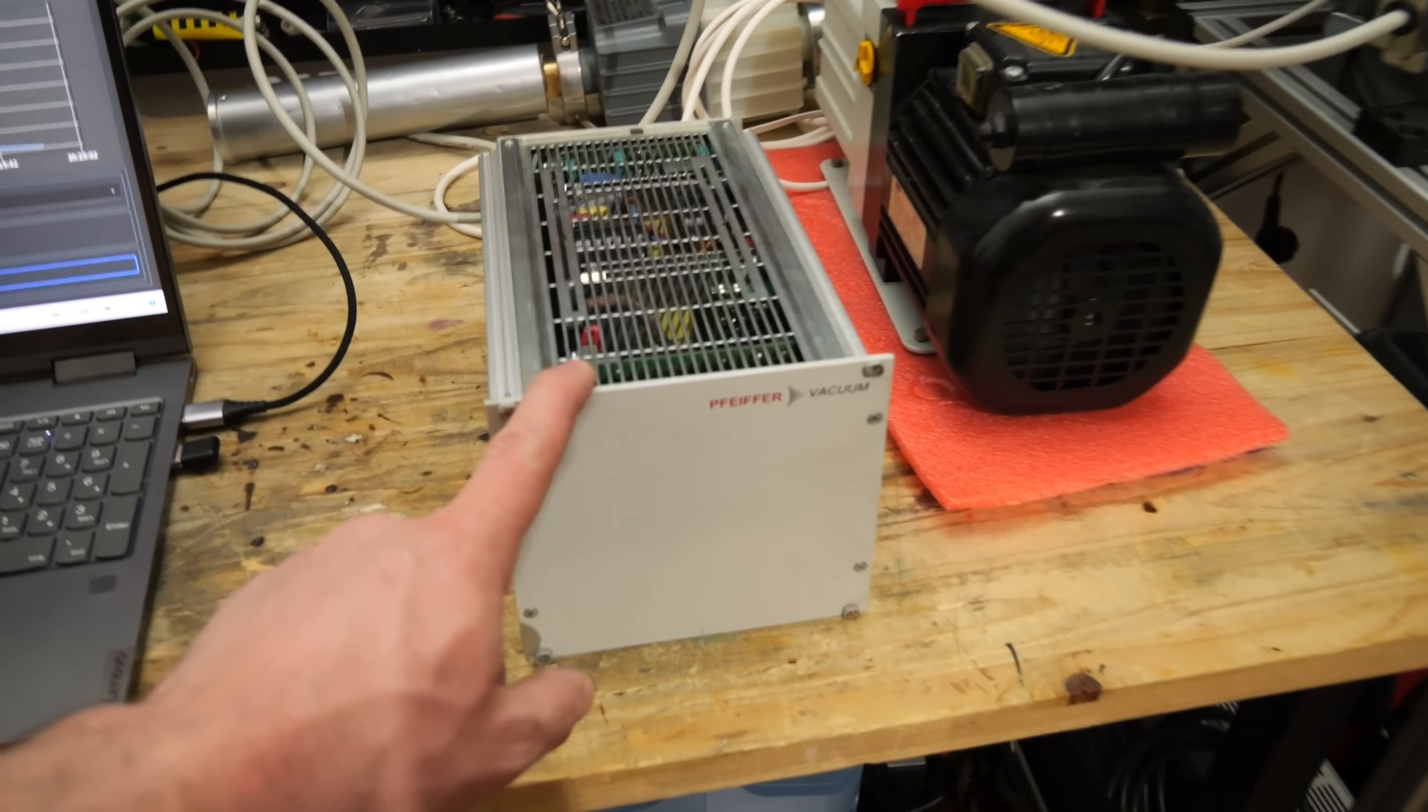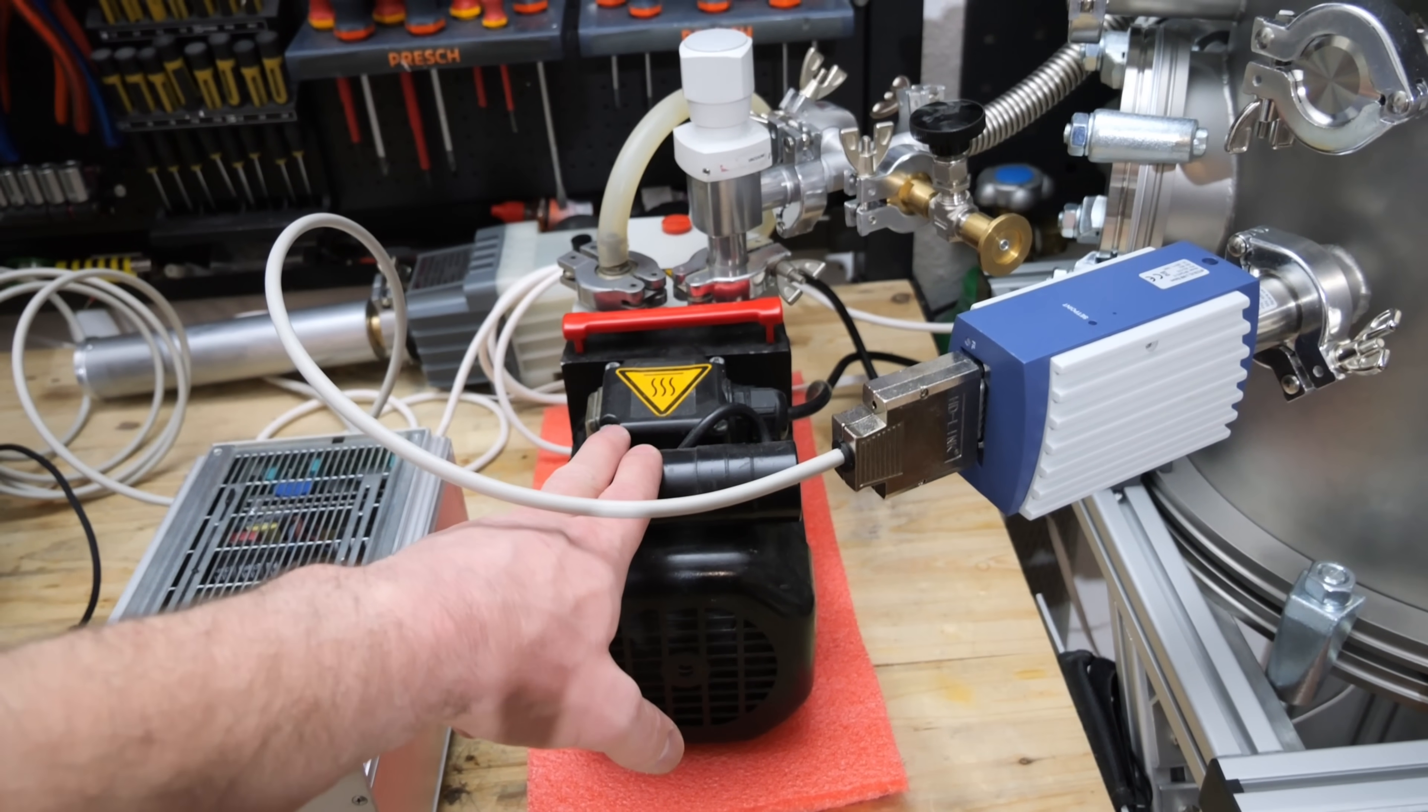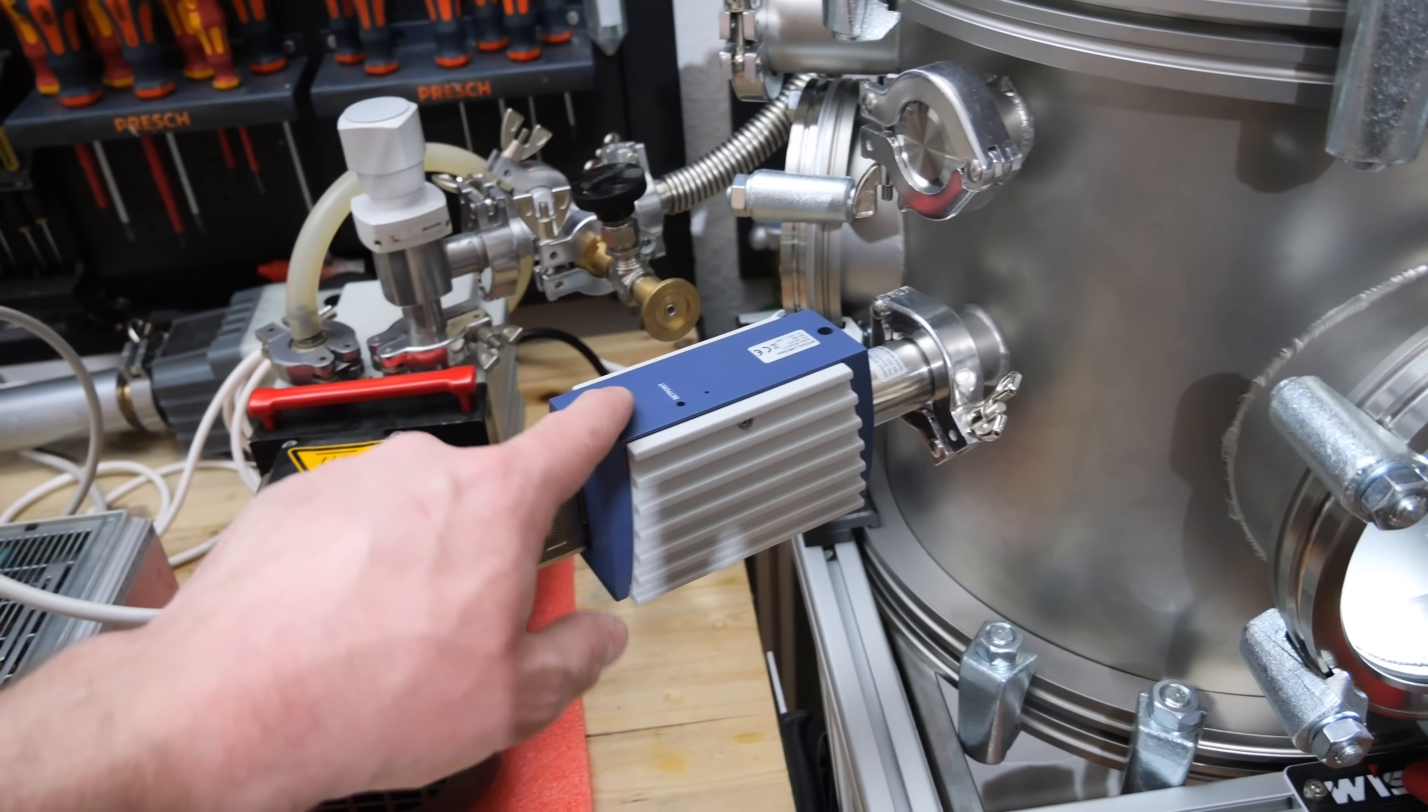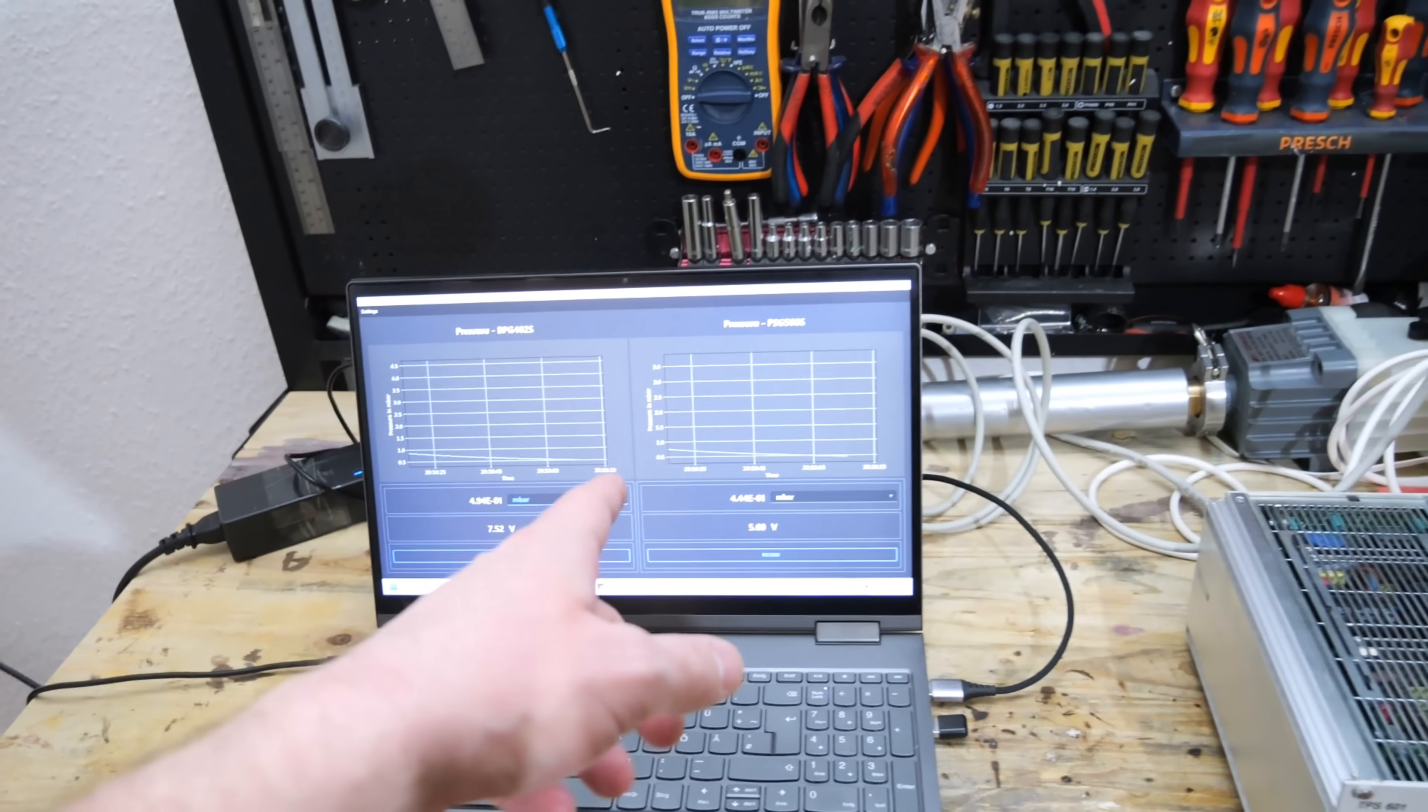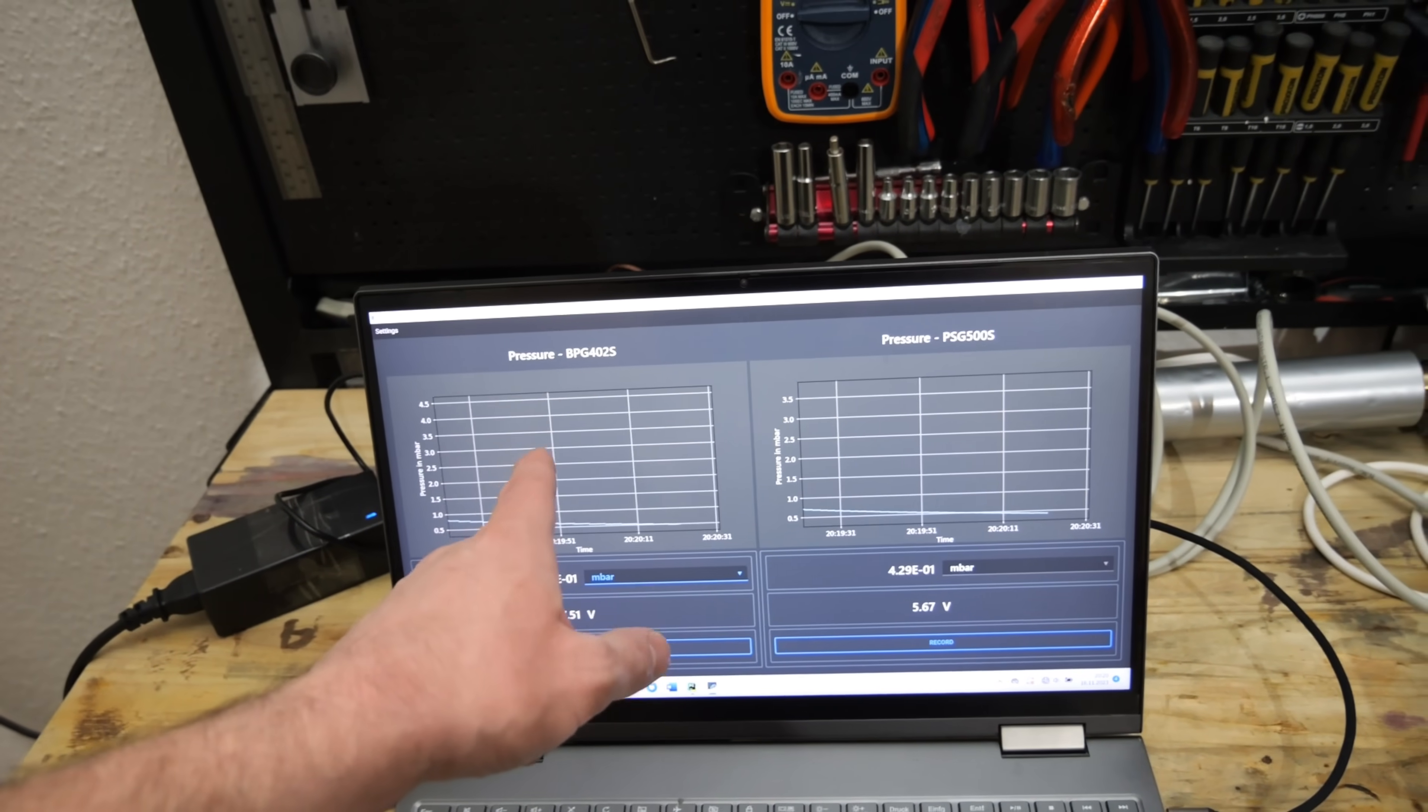Here you can see the controller for the huge turbo molecular pump. I'm using my Pfeiffer rotary vane vacuum pump as a roughing pump, and I have two vacuum gauges. The BPG402S and the PSG500S at the bottom right there. The PSG500S won't be able to record pressures at a certain point, so then I'm going to rely on the BPG.